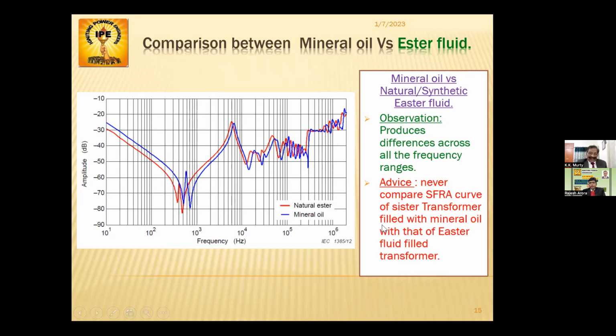So what is the advice? Never compare the SFRA curve of a sister transformer filled with mineral oil with that of one filled with ester oil. Transformers may be of the same design, but one should not compare a sister transformer with a different oil, mineral oil versus ester oil. So this is the advice.